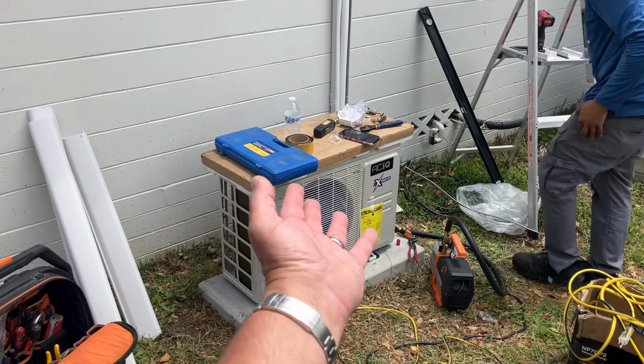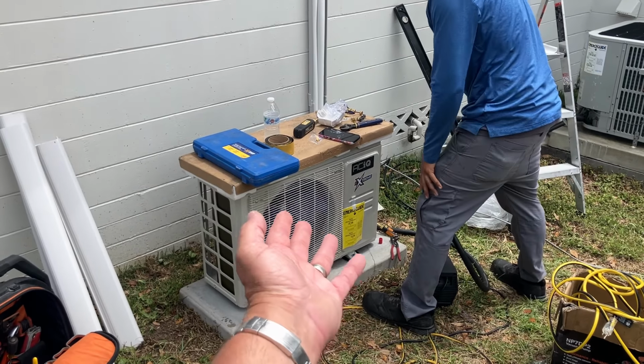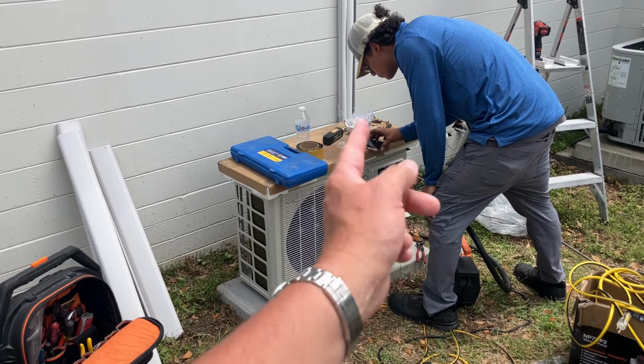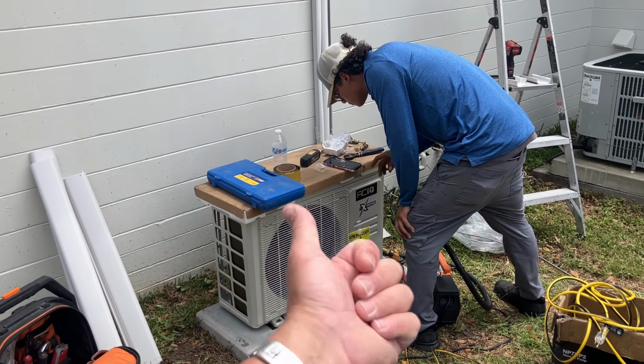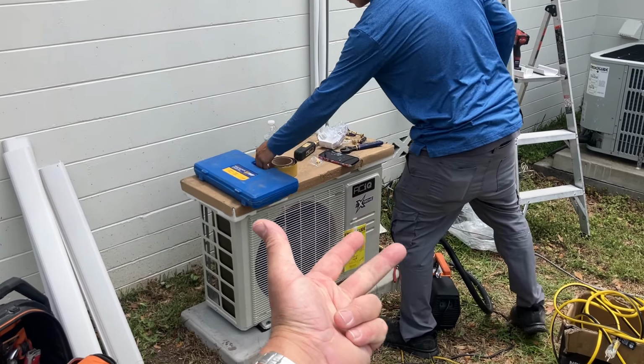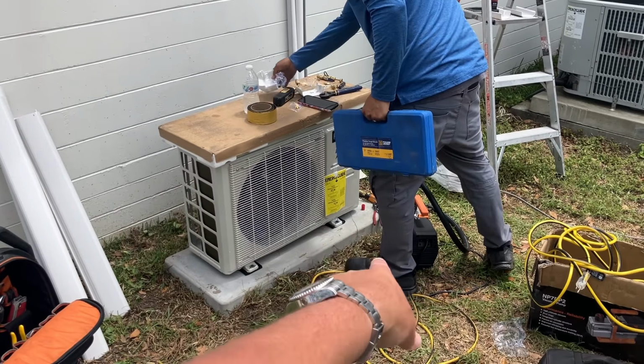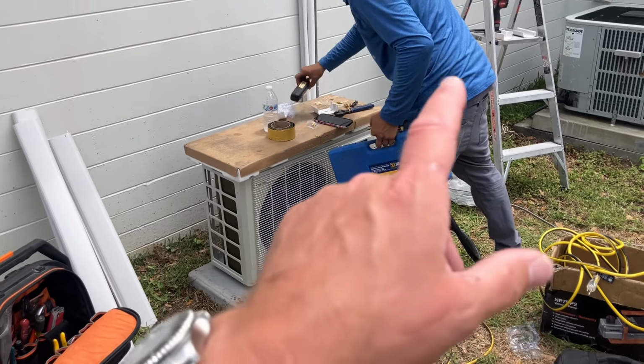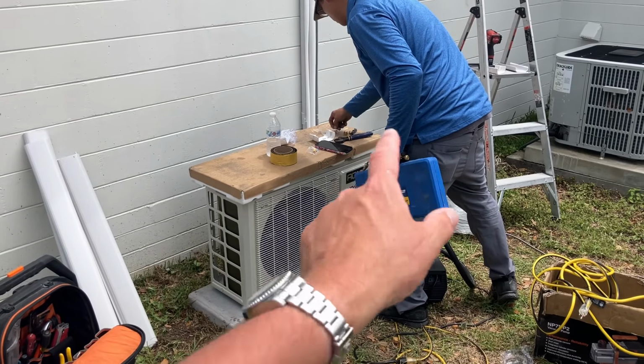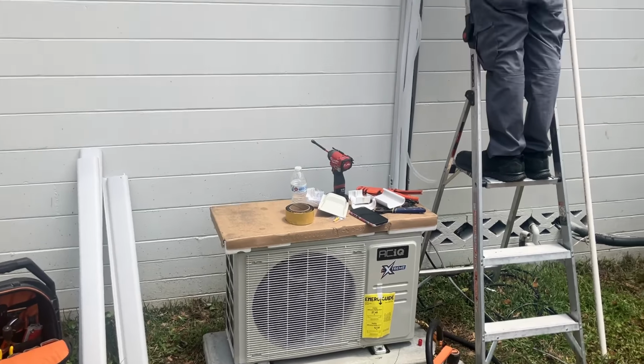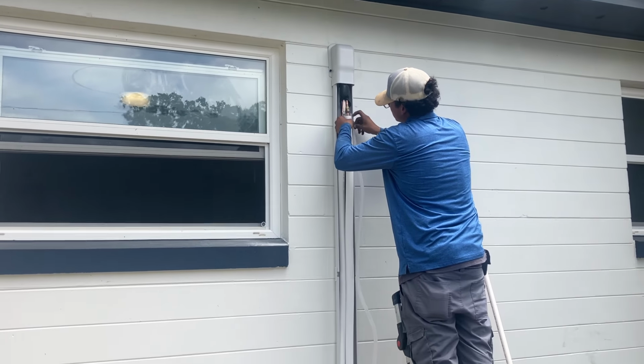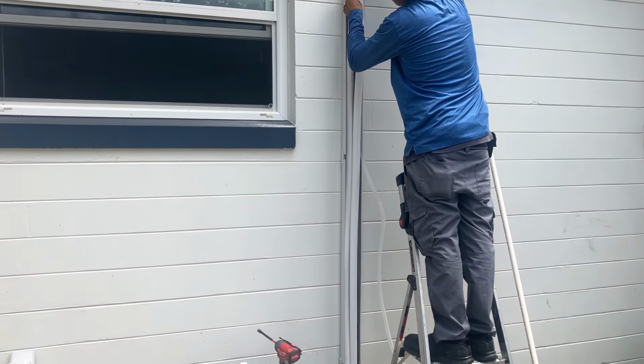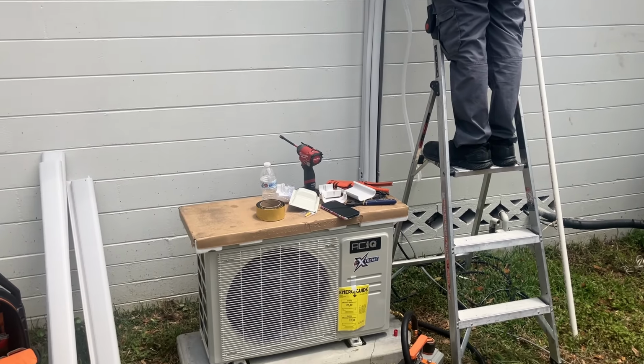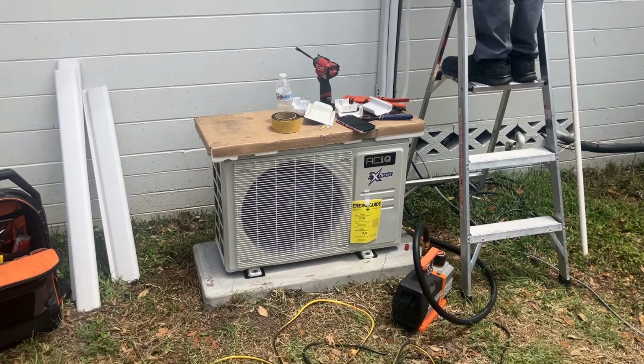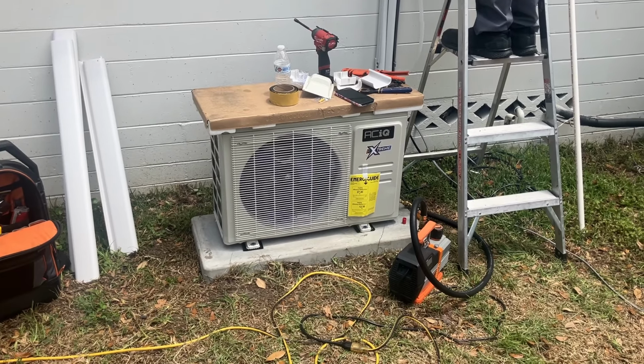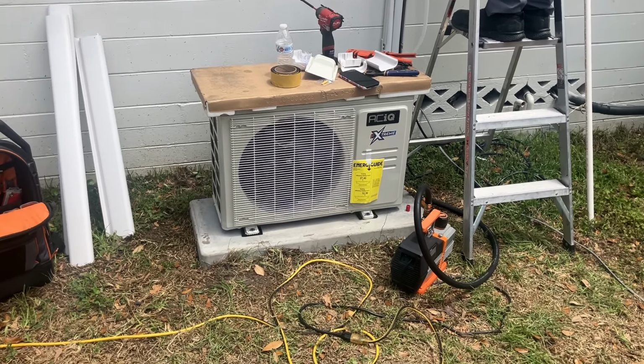And it gives the fellas an opportunity to finish up the install by doing the electric. As long as we keep pulling down a vacuum, we can run our disconnect, our whip, our surge protection device, start cleaning up, and leave this vacuum pump on for as long as possible. Let this be the last thing you take off and bring back to the truck. Juan is finishing up the installation by running that drain hose down the inside of the line hide to the ground. You may think we're almost done, but now comes the most important part of the job.